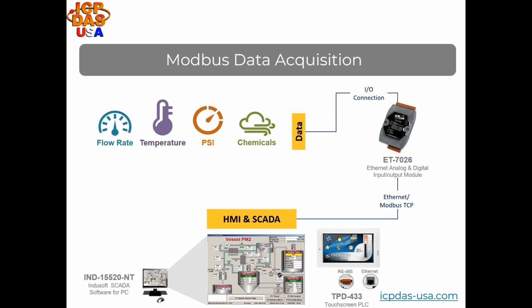In this picture here, you can see our ET7026 Modbus TCP-based data acquisition module has sensors connected to it, and data is collected and put into registers. A computer running SCADA software is connected over Ethernet and collects the measurement data from ET7026. That's a Modbus TCP-based data acquisition module with analog and digital inputs and outputs. The TPD433 Modbus TCP-based touchscreen controller is also connected to the system over Ethernet cabling and displays data from the system.